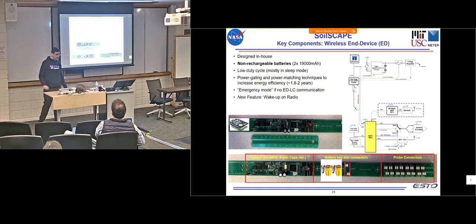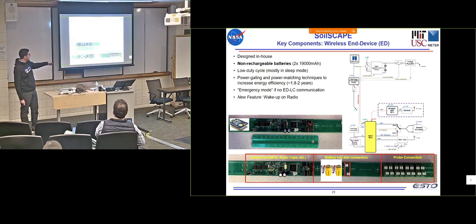This is the wireless end device, about 30 inches long. Going from right to left, these are where we connect our probes - we have 8 of these, 4 can handle digital probes, 4 will do analog probes. This is where we put our D-size batteries, about 19,000 milliamp batteries, so pretty high capacity by themselves.